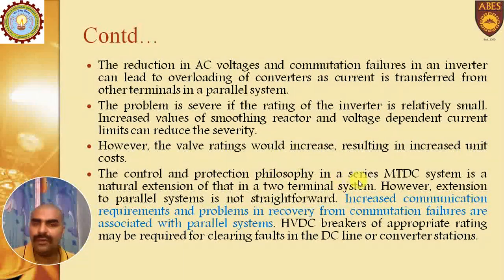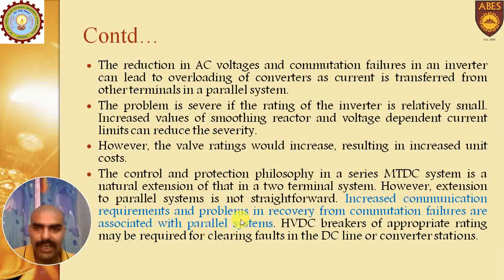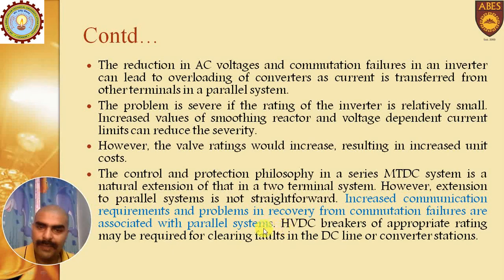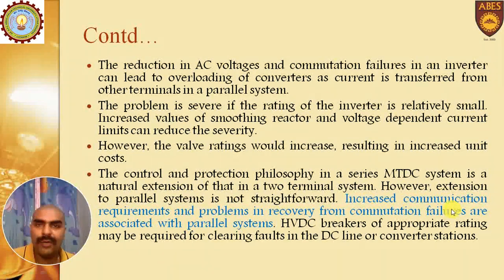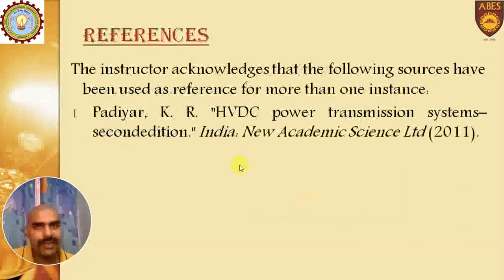The control and protection philosophy in a series MTDC system is a natural extension of the two-terminal system protection — the same protection system can be extended to a series MTDC system. Increased communication requirements and problems in recovery from commutation failure are associated with parallel systems. In a parallel MTDC system, communication requirements increase because more communication signals have to be sent to the control station. Problems in recovery from commutation failure are also main issues associated with parallel MTDC systems.